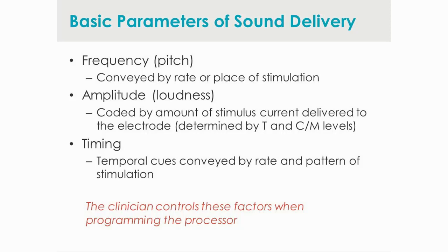Another important cue for speech recognition is amplitude or loudness. In a cochlear implant, we code loudness by delivering a current level to each electrode — a lot of current sounds loud, less current sounds softer. The third important parameter is timing. As speech changes over time, amplitude, frequency, and temporal cues — conveyed by the rate and pattern of stimulation — all change together. All three parameters work together to convey important speech recognition cues, and we have control over these factors when programming the patient's processor.